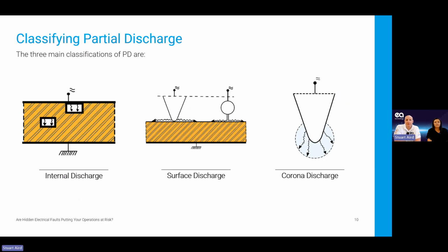So we have internal partial discharge. An internal partial discharge is a void within your insulation. You've got an HV conductor, and you have something around it like rubber or EPR, or cast resins in transformers and bushings and things like that. Cable terminations will have XLPE type cables.